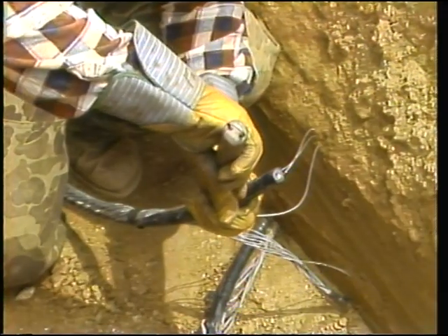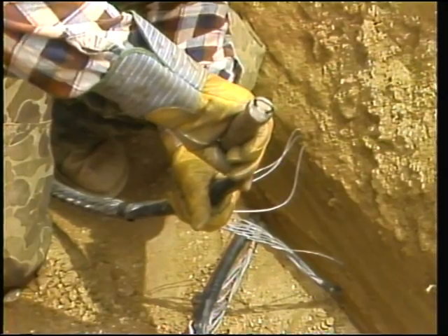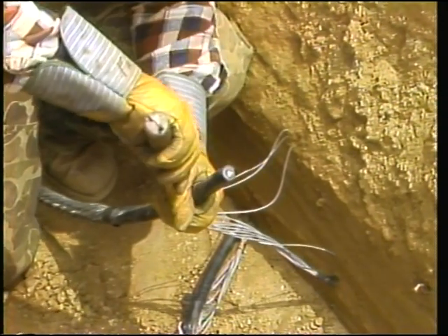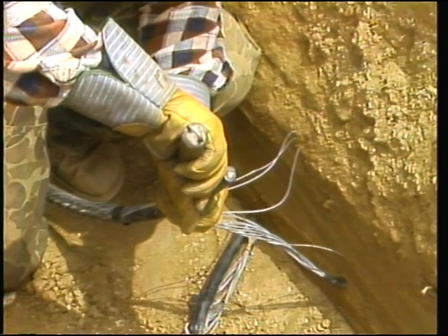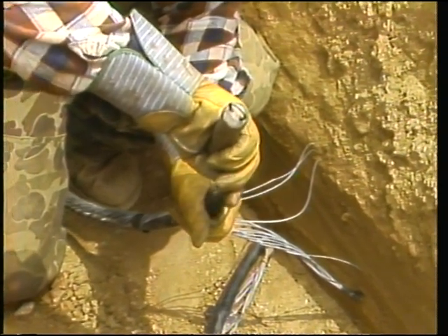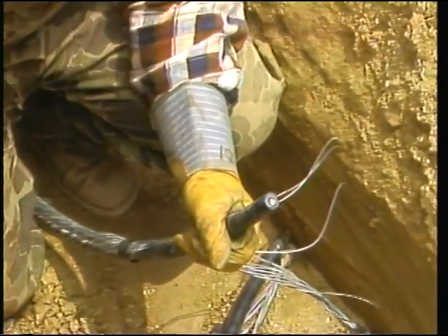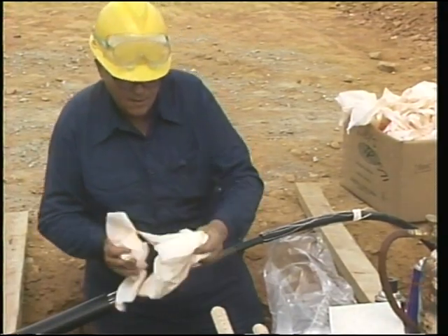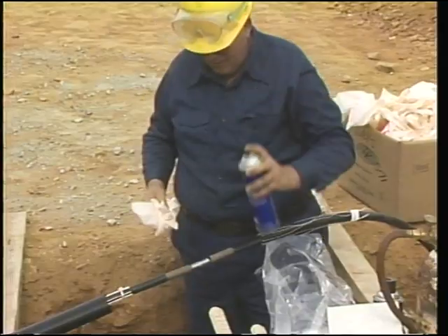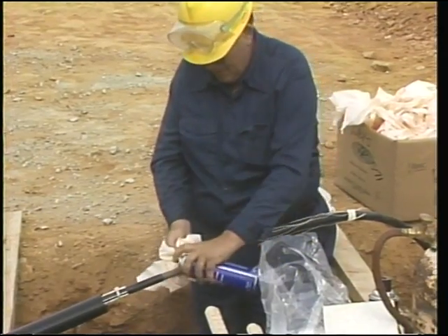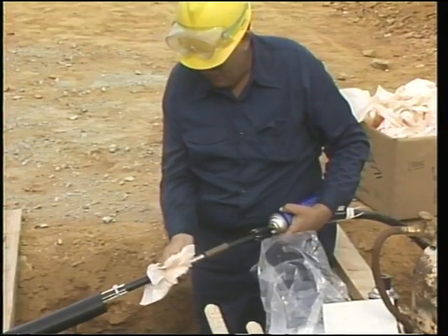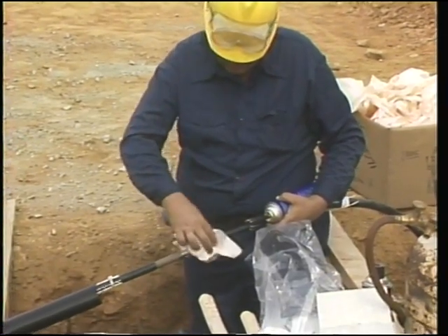A cable splicing is basically taking two cable ends and joining them together while making sure that the original cable design characteristics are restored. First, a cable must be prepared by removing the individual cable layers and preparing each for splicing. Now, it's important that when you're doing this, the layers below the one being removed not be damaged. Nicking the insulation can weaken it, thus defeating the purpose of the splice. It's also important to keep the splice area free of contaminants that could create a conductive path over the splice. Conductivity over the insulation can defeat the insulation's purpose and make the splice weak or ineffective.